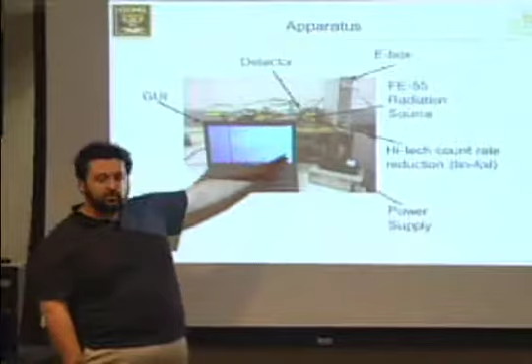This is the histogram from one of Marcus's slides. This was actually a histogram of live data. We set the high voltage in the detector to roughly 1.8 kilovolts. We set our event discriminators to about 500 millivolts. The noise floor on this system is a little high. There's definitely future work to reduce that noise floor. And we enable the interrupts inside the system. And you can see here in the histogram that we have a very clear, almost Gaussian peak, which is what data should look like for a given X-ray source.